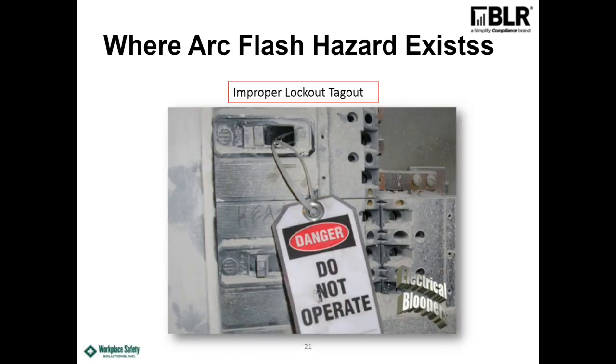Okay, lockout tagout. So you can see this particular lockout tagout is in a high dust area. They've got some breakers with some open bus work on the right. They've got a paper clip that they're putting into the breaker. This place was a very scary place, and you see these kinds of things out there. And it's amazing what happens. Well, we've always done it that way. You've probably heard that a million times yourself, but it doesn't mean it's going to be the best way to go. This is where you're going to get statistics.